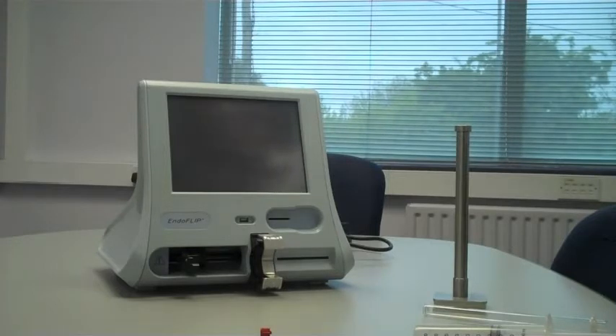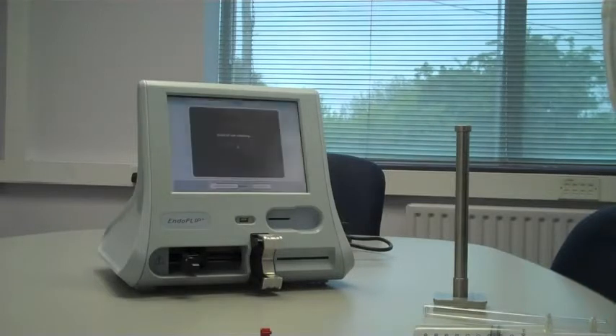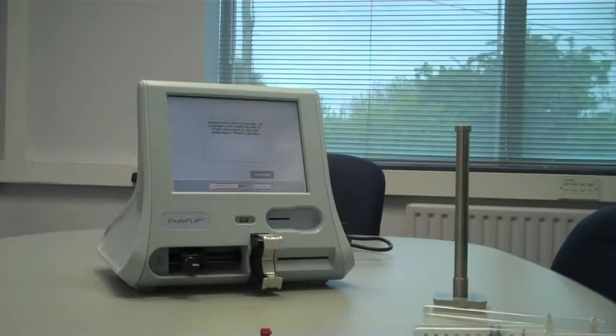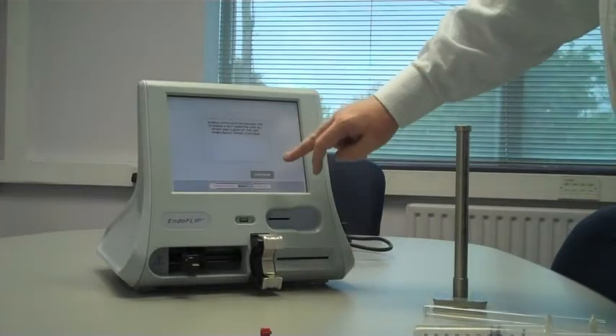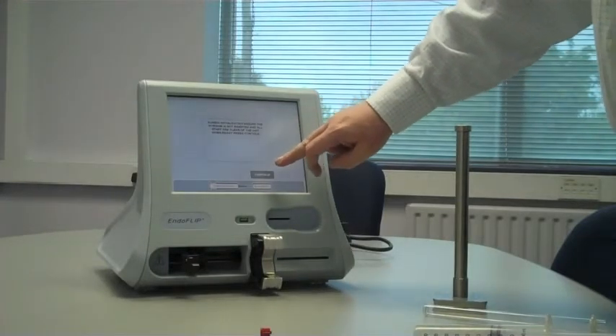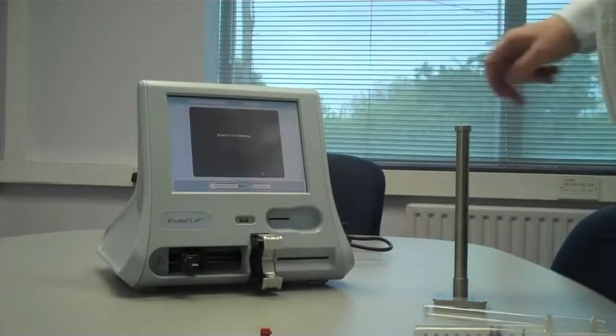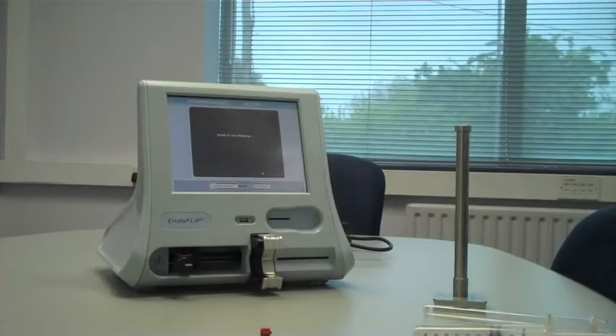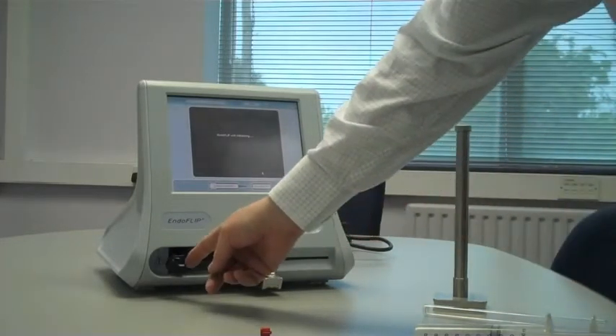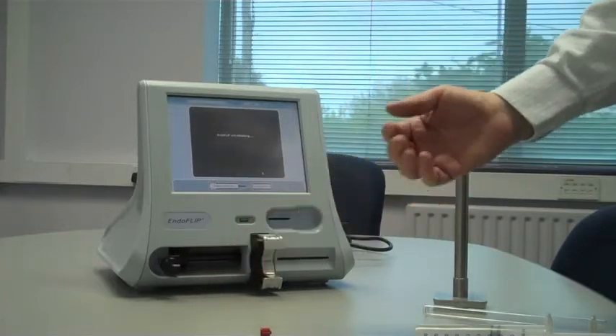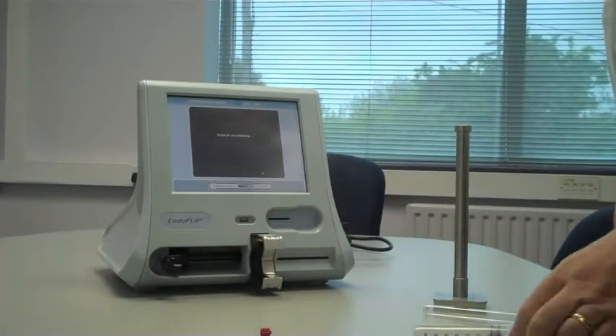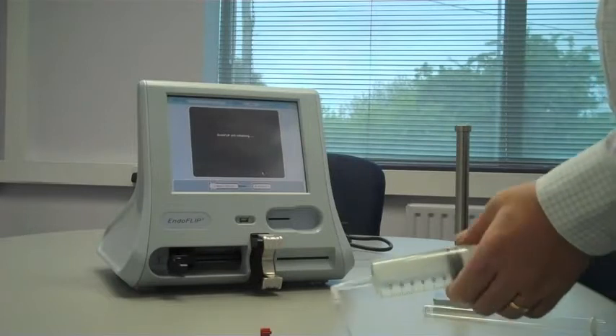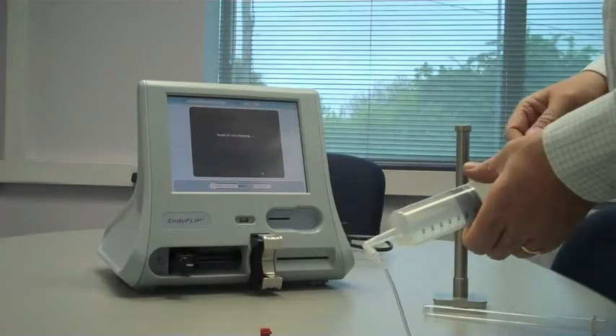It takes approximately 15 to 20 seconds to power up. And so this is the warning I mentioned here about not having anything connected. You hit continue, and you will see here that the syringe plunger moves back and then homes back to the position that should always match the syringe that you are putting in.